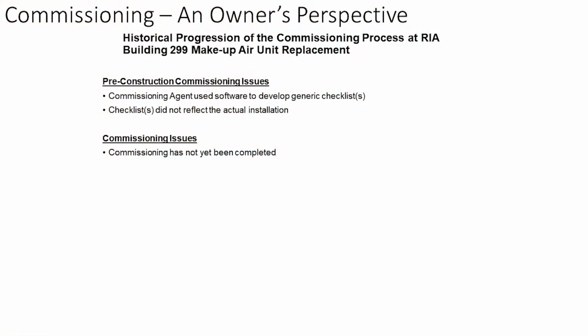The commissioning firm, I don't understand what I wrote here, but I had worked with the commissioning firm before, but not with this individual. Again, we had problems with generic checklists. He used the same software, must be very popular with the commissioning group. And the checklists, I actually did get a couple of the pieces of equipment did not reflect the actual installation. Matter of fact, the makeup air units that were sent to me, the checklists were for a gas-fired DX unit, whereas we had a hot water with no cooling. Commissioning has not yet been completed on this project. This is just finishing up.